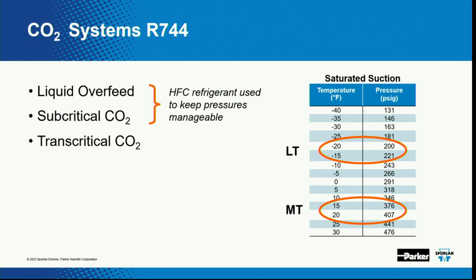On a low temp rack or low temp case, negative 20 degrees, this is basically a pressure temperature card here. Negative 20 degrees Fahrenheit is equivalent to 200 PSI. And on a medium temp at 20 degrees, you're looking at almost 400, or around 400 PSI. So those are pretty high pressures.